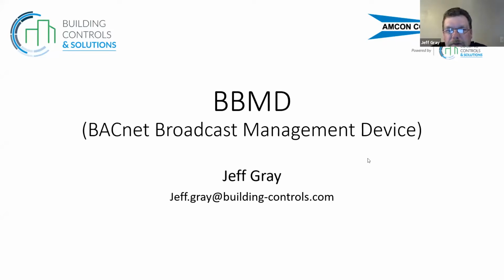We're going to be going over BBMDs, which stands for BACnet Broadcast Management Devices. They're used when you're going from one network to another on IP networks: school districts, multi-campus, multi-building campuses. It allows you to have one front end in one building and have the whole system communicate through the different subnets up to it. I'm Jeff Gray with Building Controls and Solutions.